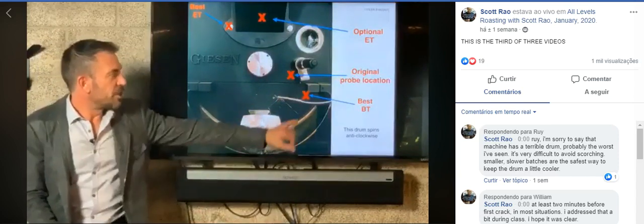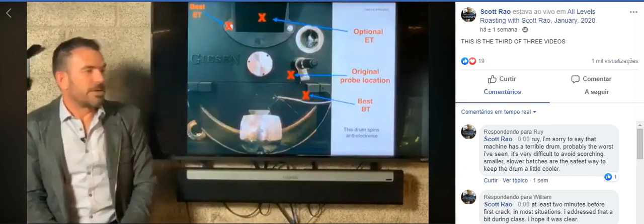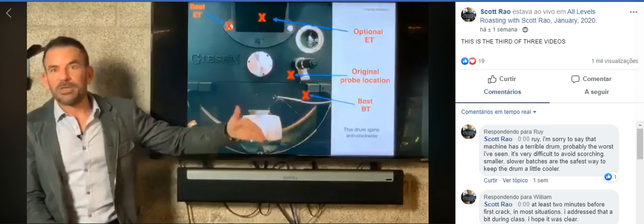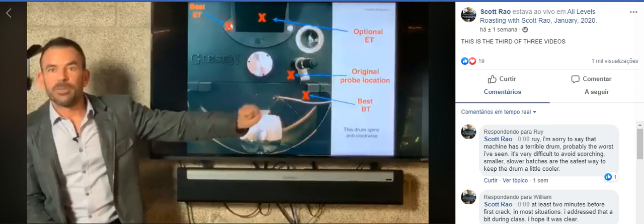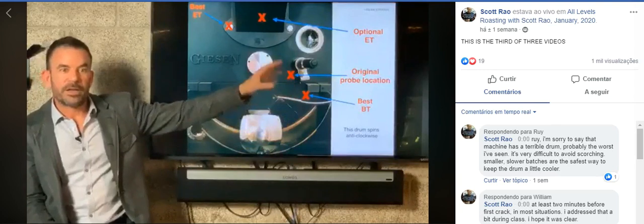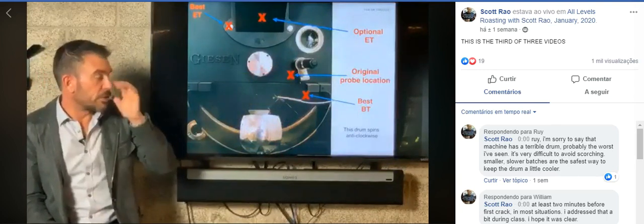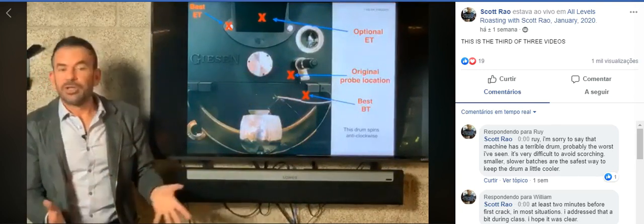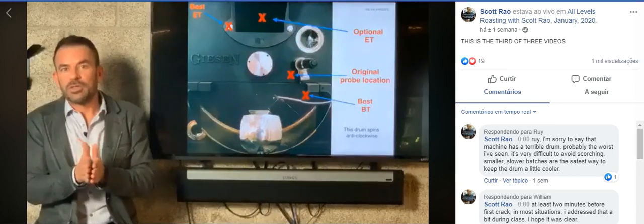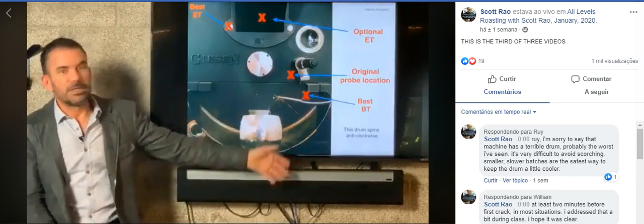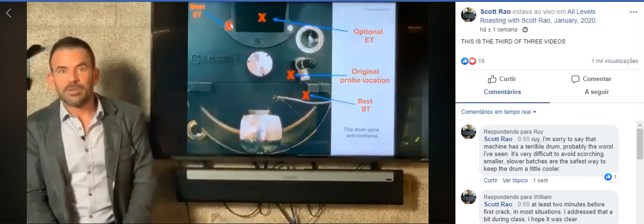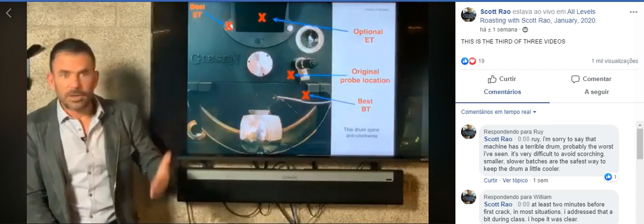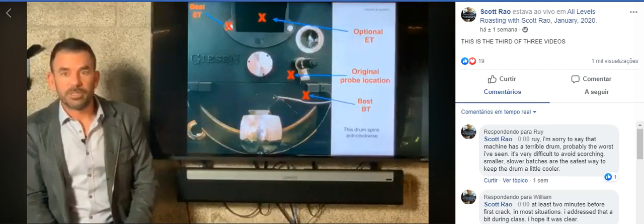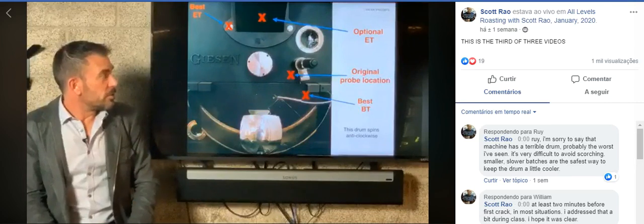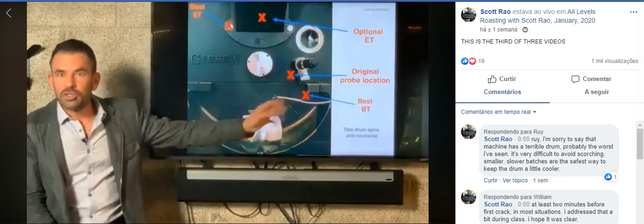So generally speaking, if the probe is about 2 to 3 centimeters from the faceplate, 2 to 3 centimeters from the inner drum edge on smaller machines, maybe add an extra centimeter on large machines, let's say larger than 30 kilo, that's pretty good, in the sense that you don't want to be too close to the metal, because the faceplate is not going to be as hot as the air in the drum most of the time. You don't want that to overly influence the bean probe tip. So that's a good general recommendation.